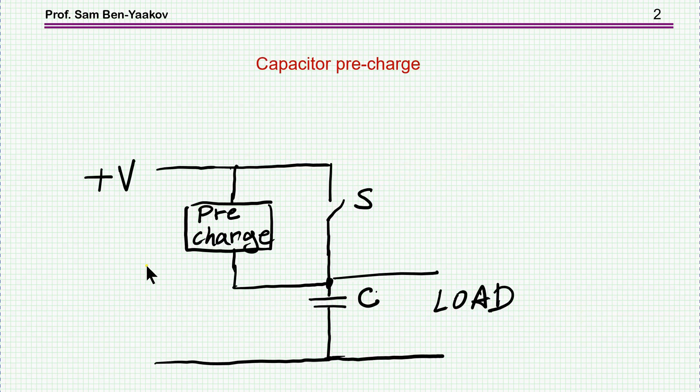We are concerned here with the pre-charge circuit, which is required in order to avoid high inrush current. If you just connect the voltage to a capacitor, you're going to have a very high peak current which could be dangerous. So you need a pre-charge to charge the capacitor in a lower current.